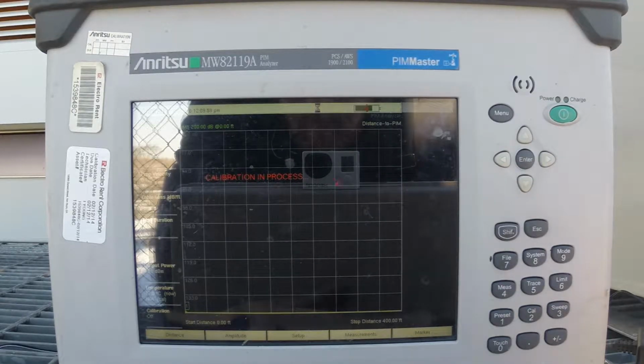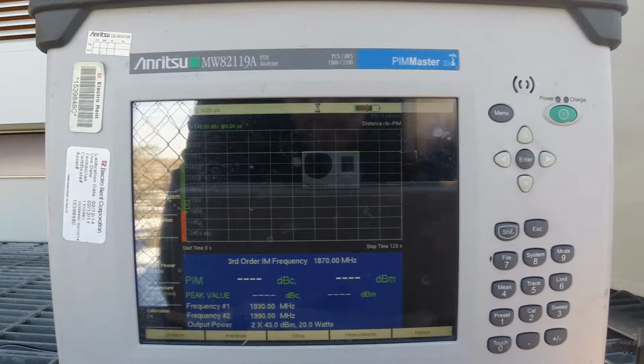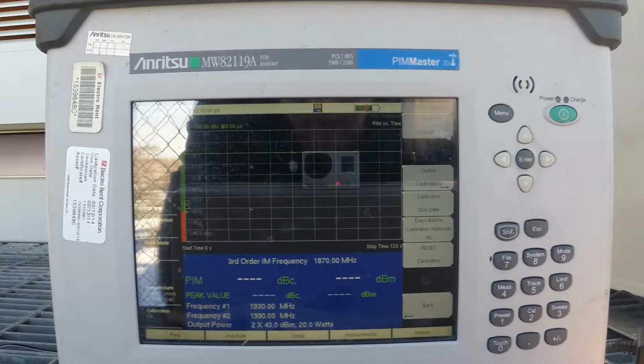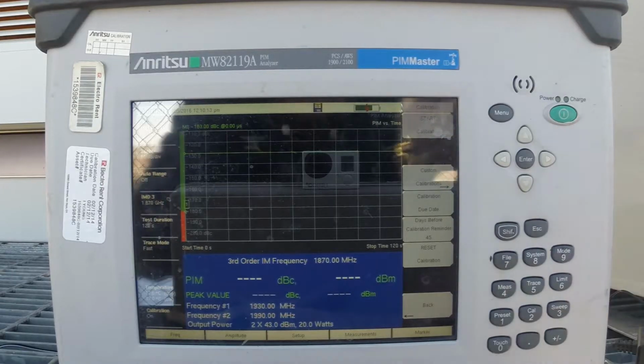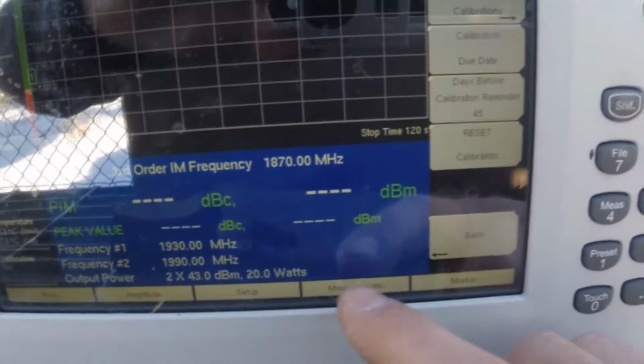And along with that PIM standard, we can use that to verify that our calibration is good and our unit is measuring correctly. Since we know that's a known source, it is set at neg 80 dBm. So once we go all green, our soft keys come back up here. We can go down to measurement, down here on the soft key, or you can go shift 4, and that'll also pull up measurements. Right now, we're set on PIM versus time, and we're set at 120 seconds.